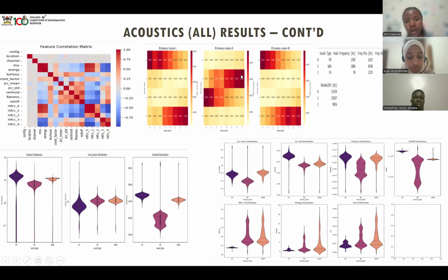And from these array images, we're able to see where the signal is. The signal is captured in different parts of the 32 channels, whereby some of the signal is captured at the edges and some in the middle. And from the frequency reports, we see that the partial discharge has a frequency ranging from 2,000 Hz to 15 to 16,000 Hz. White Gaussian noise has a signal ranging from 4,000 to 19,000 Hz, and the chaps have a signal ranging from 1,000 to 10,000 Hz.